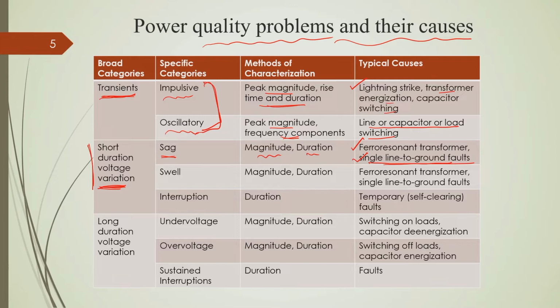Okay. So, single line to ground fault is a very frequent fault for distribution networks, which may cause voltage sag. This voltage sag is characterized by a dip in the voltage magnitude and the duration. Similarly, voltage swell is just the opposite of voltage sag; it is basically a short duration rise of voltage, which is also characterized by voltage magnitude and duration. It occurs due to the same reasons as voltage sag, that is, ferroresonant transformer and single line to ground fault. Specifically, single line to ground fault, as I said, is very common in power distribution networks.